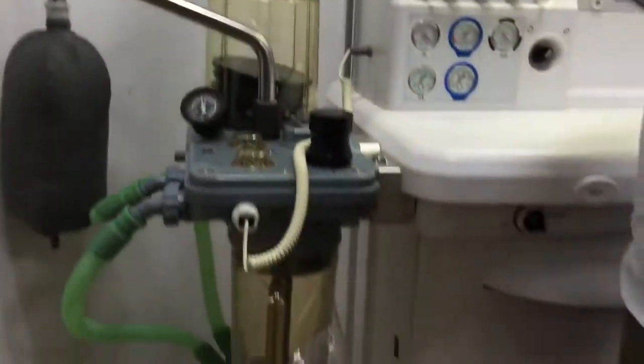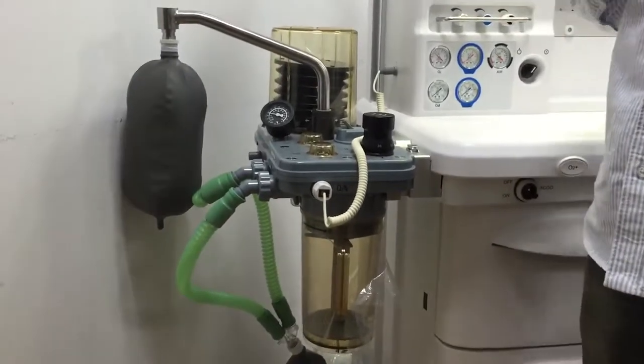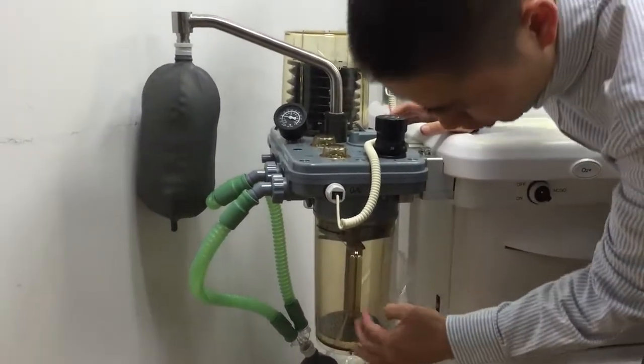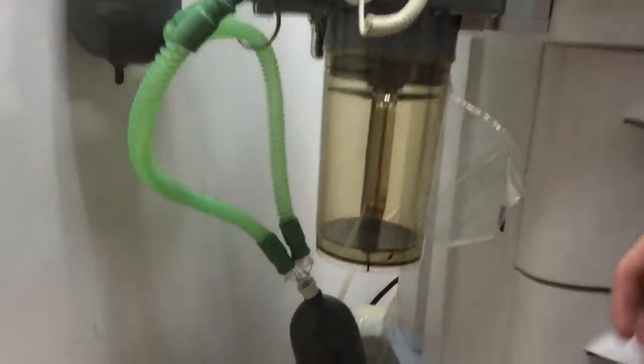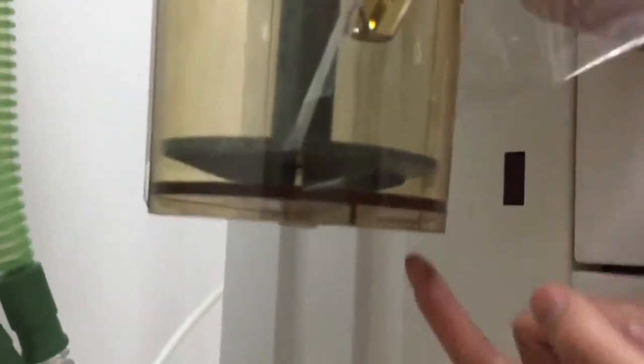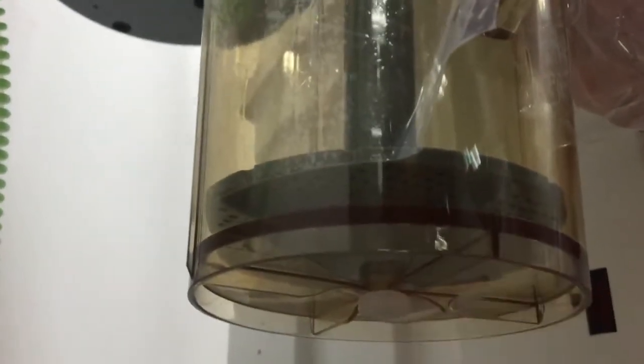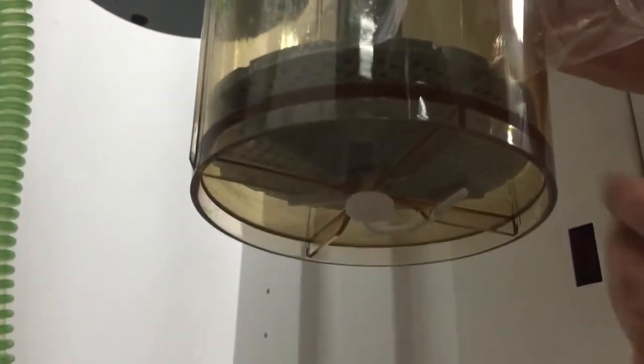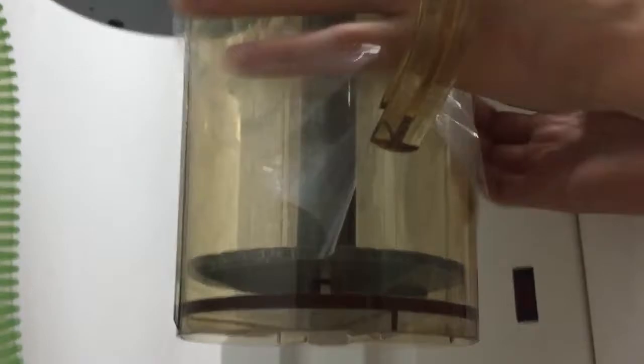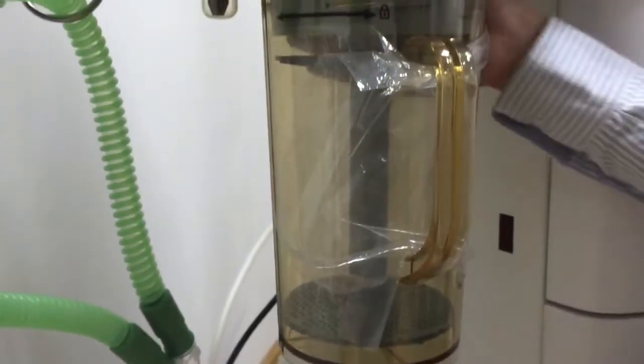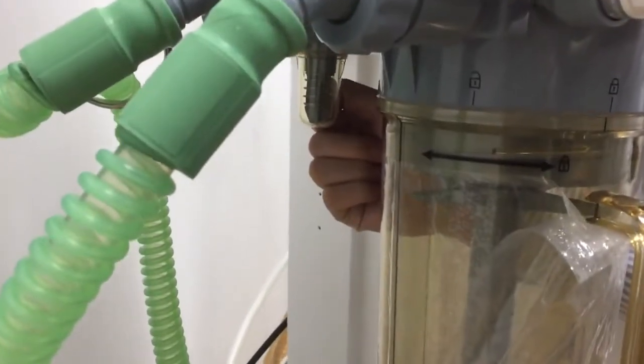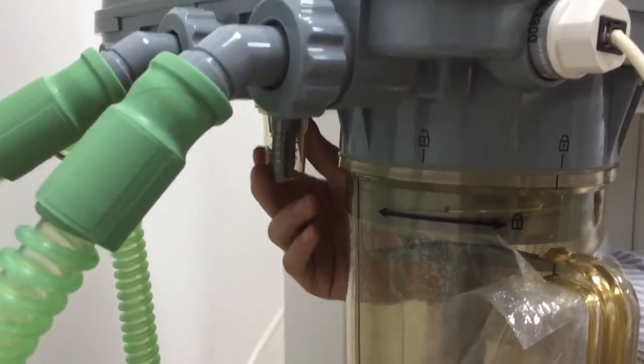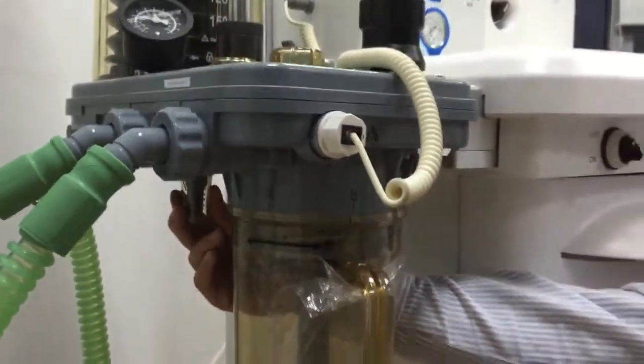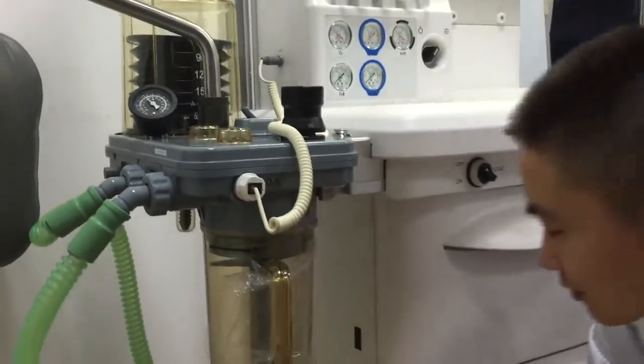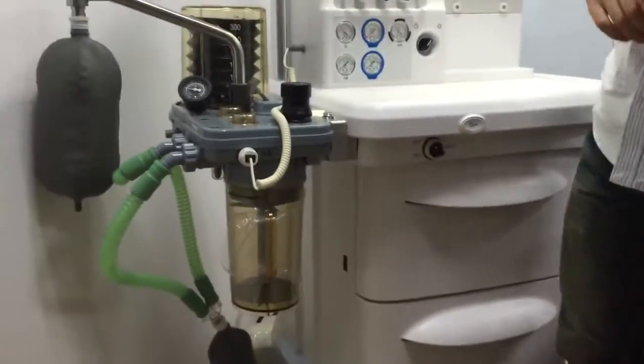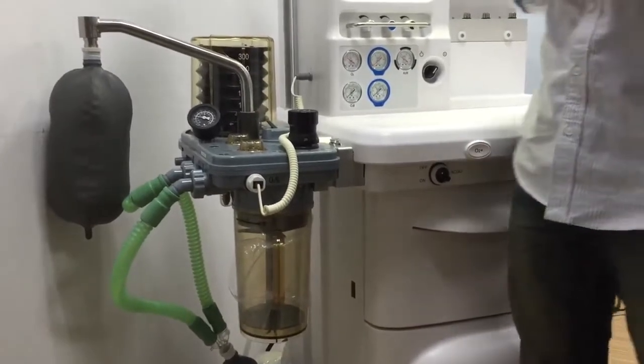And by the operation use, usually we'll get some condensation, like the water trapped on the bottom side of the canister. Then there is a pot. We can simply remove the pot to drain the condensed water out and keep using the absorber system. And also during the bypass, we still have one more water trap designed here to trap all the condensed water in the absorber system, and we can remove it to drain out. But maybe you will think about why we need so much condensation protection for the machine.